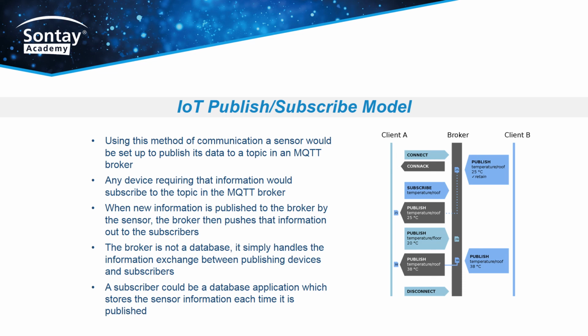As an example, a space sensor may publish its data to a space temp topic at the broker. A heating control application running on a server and a database application may be subscribed to this topic, and each will receive the new data as it's published. The database application will store the new value with a timestamp, whilst the heating control application will use the data to switch the heating on or off, possibly by publishing a status to the broker, which is subscribed by a smart actuator.